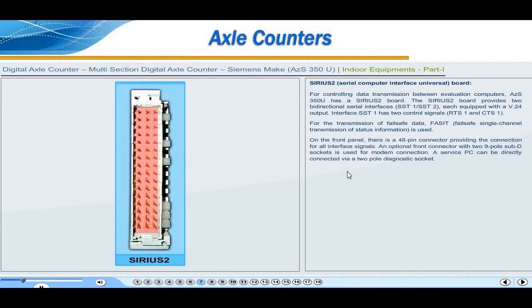On the front panel, there is a 48-pin connector providing the connection for all interface signals. An optional front connector with 2 9-pole sub-D sockets is used for modem connection. A service PC can be directly connected via a 2-pole diagnostic socket.